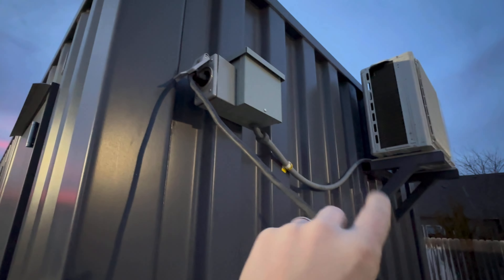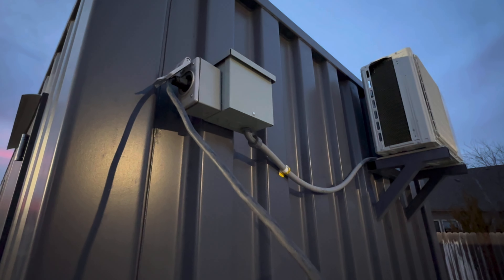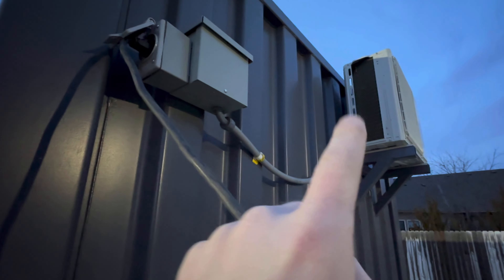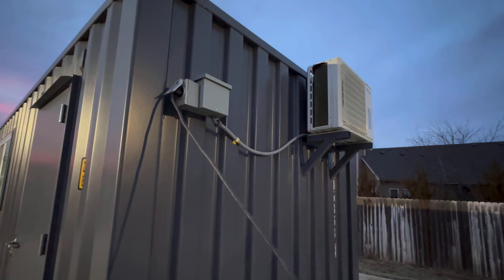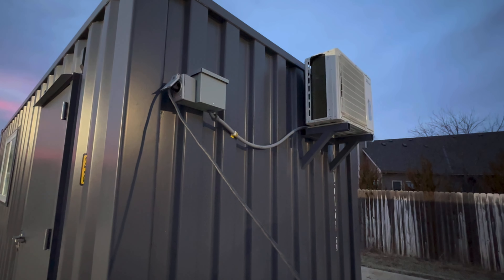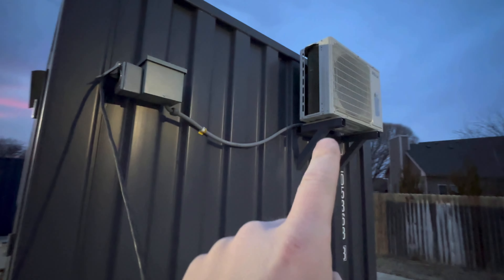What we have done here — 115/120 volts, I'm going to refer to it as 120 from this point forward. A 120 cord is 15 amps generally on any breaker. The mini split pulls about eight to nine amps running full out, so we've got about six amps left over for computers, TVs, and whatever else. That's plenty.